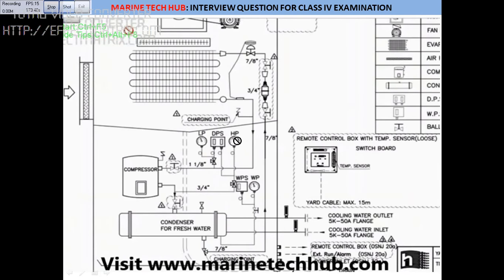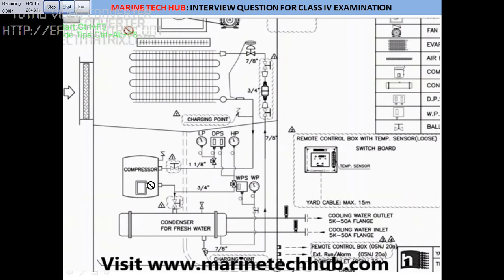We have HP and LP pressure trips on the compressor — when pressure is too high, it trips. There is a low pressure trip when gas is insufficient, a high pressure trip, and a water pressure trip if cooling water is not flowing. The gas gets compressed; if some liquid enters the compressor, it will cause sweating. If you see a lot of sweating, check the sight glass — if you see bubbles coming through the sight glass, that is a key indicator.